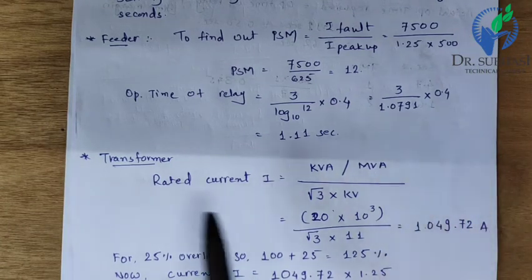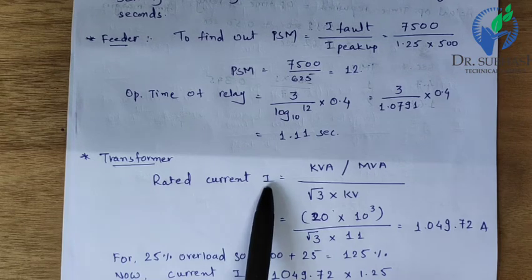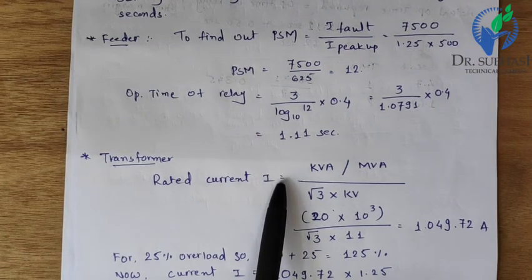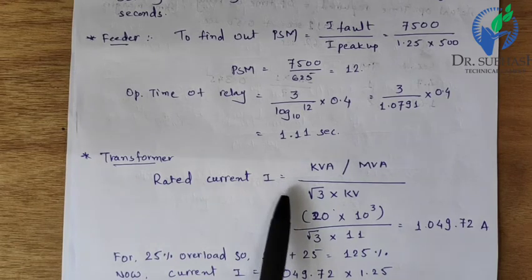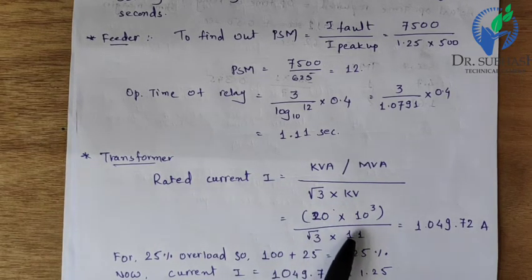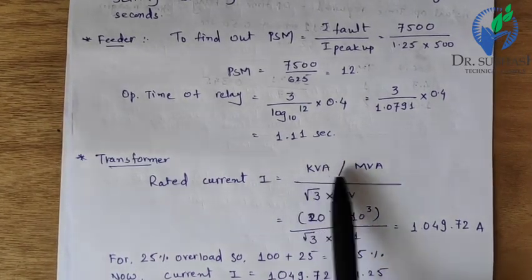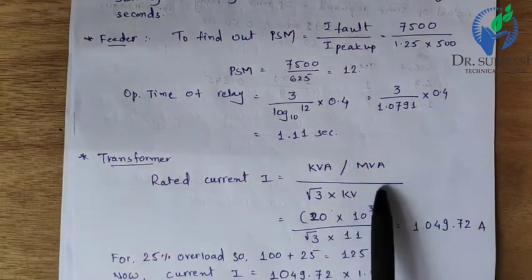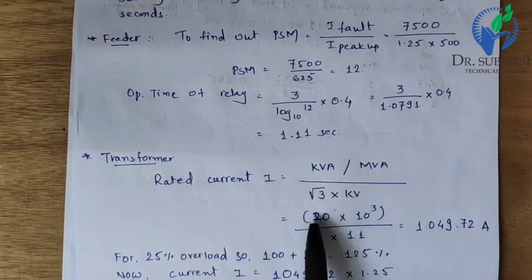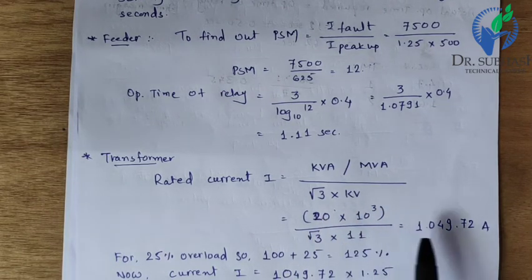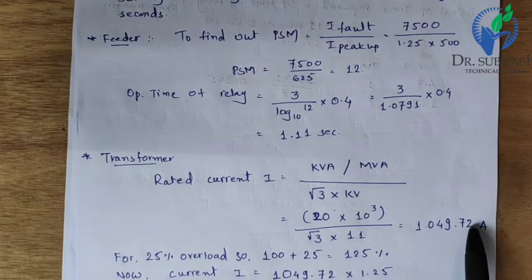For the transformer, we find the rated current from the 20 MVA rating and 11 kV voltage. Using I = MVA / (√3 × kV) = (20 × 10³) / (√3 × 11) = 1049.72 A. This is the rated current of the transformer.